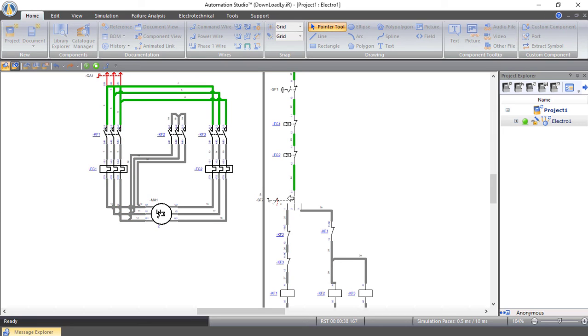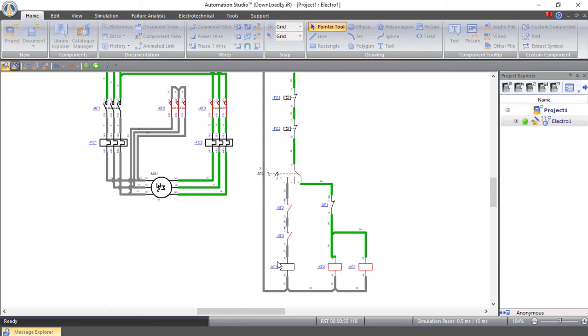If we connect it in the other direction, it will make this motor work as star-star. And as you can see, KF2 and KF3 are open in the path of KF1 to ensure that it will never work at the same time. So now we have the high speed, and when we open it and choose the other direction, we will have the low speed.